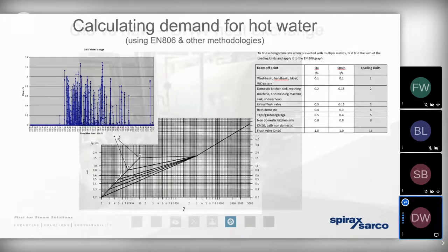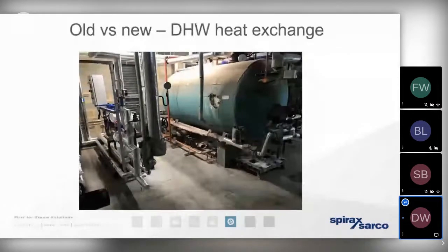So old calorifiers, storage systems, such as the one we can see on the screen at the moment, they're going to bring any steam using site a number of different operating issues. It's the storage of hot water that may never be required. So we've got that inefficiency. We've got a further inefficiency because we're going to have a lot of heat energy radiating out into the plant room. We're taking up quite a lot of plant room space that could be set aside for other items of capital equipment or for production purposes. We get a very, very inefficient rate of heat transfer.